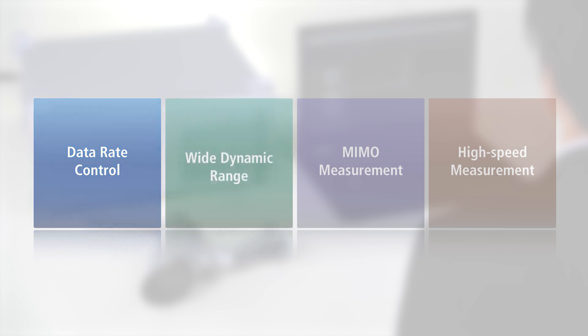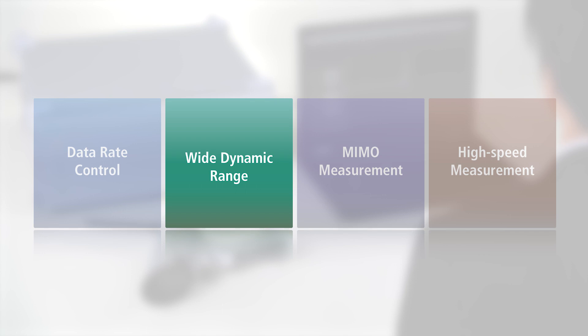Second is wide dynamic range. Measuring DUT using tester with a wide dynamic range supports stable measurements even for low power, wideband, wireless LAN input signals. This has many benefits when tests over the air environment like antenna performance test with large signal loss and power fluctuations.